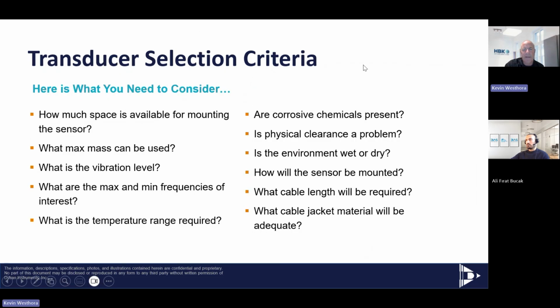The next thing I want to talk about is how to select a proper accelerometer, how to select a proper sensor. The first thing we ever talk about and look at is the size and mass of the product you're testing. Because the last thing we ever want to do is, if your test article is 3 grams, select an accelerometer that weighs 10 grams to measure the vibration of that test article, because you're going to mass load it, change the frequencies and dynamics of the test, and not get good data. So the first thing we ever look for is what space, mounting, and maximum mass the test article can accommodate.